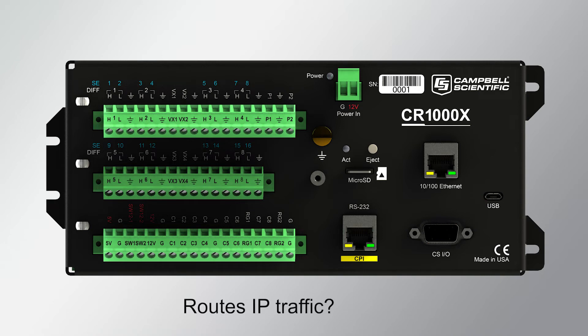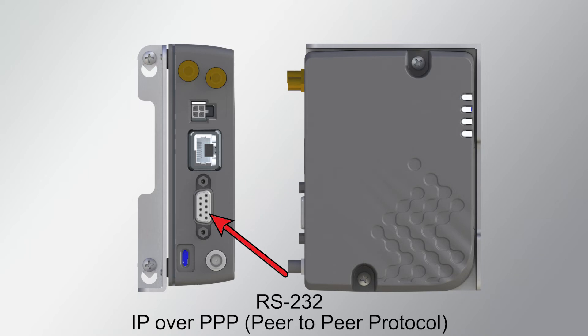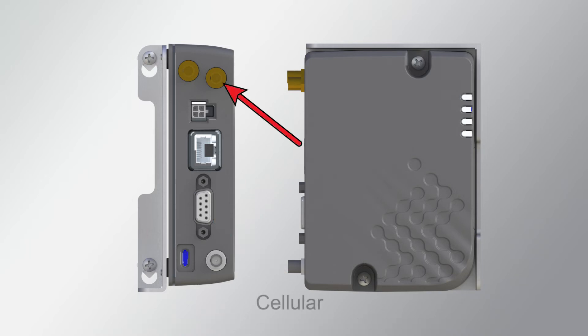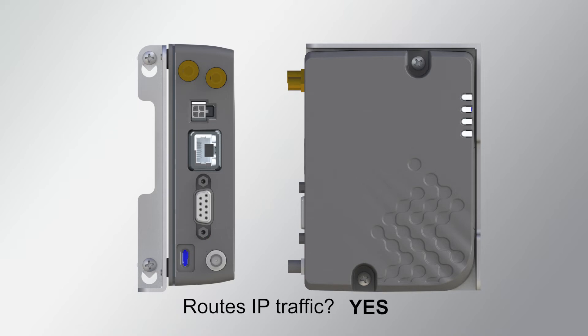It's important to note that the data logger does not route IP traffic — it can only route PAKbus traffic. In order to route IP traffic, a cellular gateway such as the RV50X must be used. The RV50X is a cellular gateway available from Campbell Scientific that supports multiple IP network interfaces: an Ethernet port, an RS-232 port for IP over PPP, a cellular module for connection to the internet, and a USB port for RNDIS, though this is turned off by default to conserve power. The RV50X does route IP traffic between its various network interfaces.